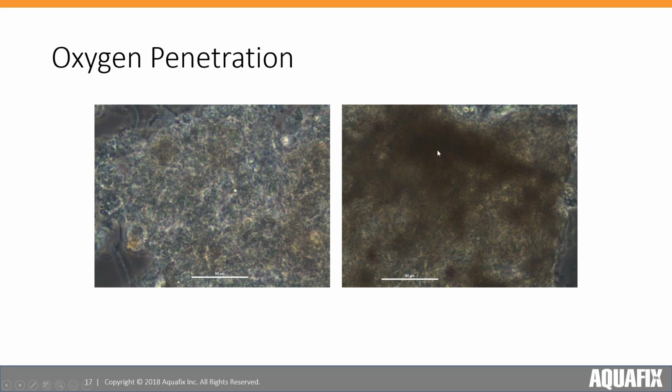That doesn't use as much nitrogen or phosphorus per carbon substrate as aerobic metabolism does, so you can get nitrogen as ammonia actually released into the water under these conditions, resulting in higher effluent ammonia. Anaerobic metabolism can also produce compounds that bind strongly to oxygen, such as hydrogen sulfide gas. And this metabolism also releases a lot of simple carbon compounds, which the heterotrophs will then use with oxygen, and that makes less oxygen available to the nitrifiers.